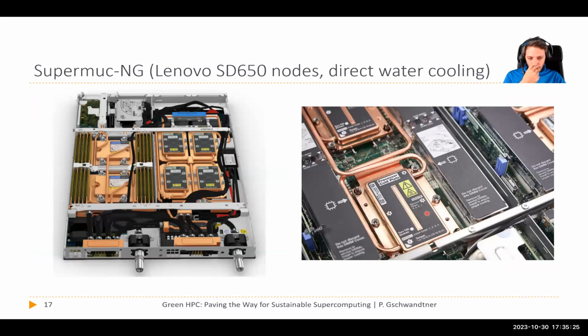And on the right, you see a photograph that illustrates how tight the tolerances are on that. Because, for example, what you see here is the processor cold plate, as they call it, which is essentially just a cooling unit. Below this thing, you have the actual CPU. And I'm not sure if this is visible on the screen share, but here you can see the order in which these 4 screws should be removed, and also the order in which the screws should be installed back. And below that, there's even the torque, how tight these screws should be fastened. All of that is precisely specified to make sure there are no leakages and to be sure that there's full contact, so you're doing the most efficient cooling possible without the CPU having to clock down because of thermal issues, for example.